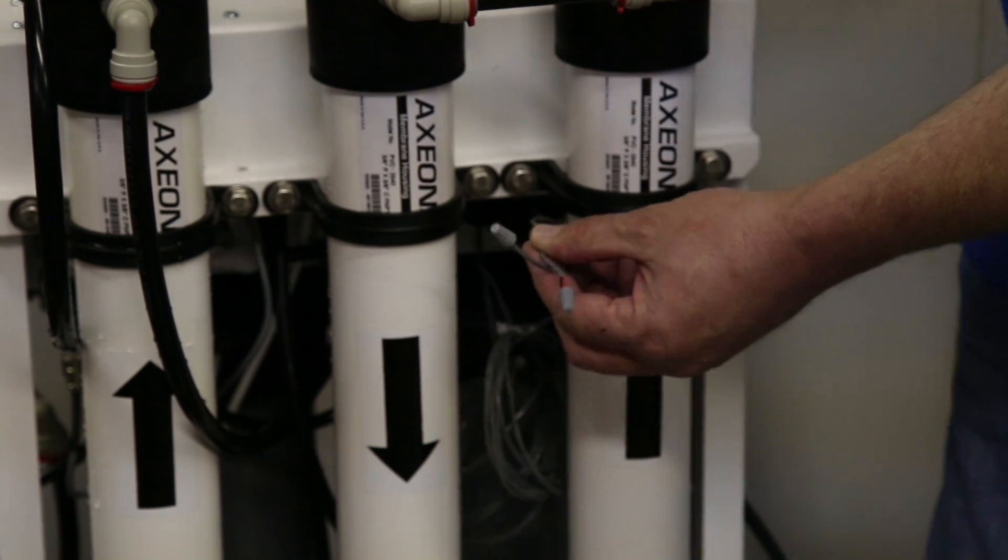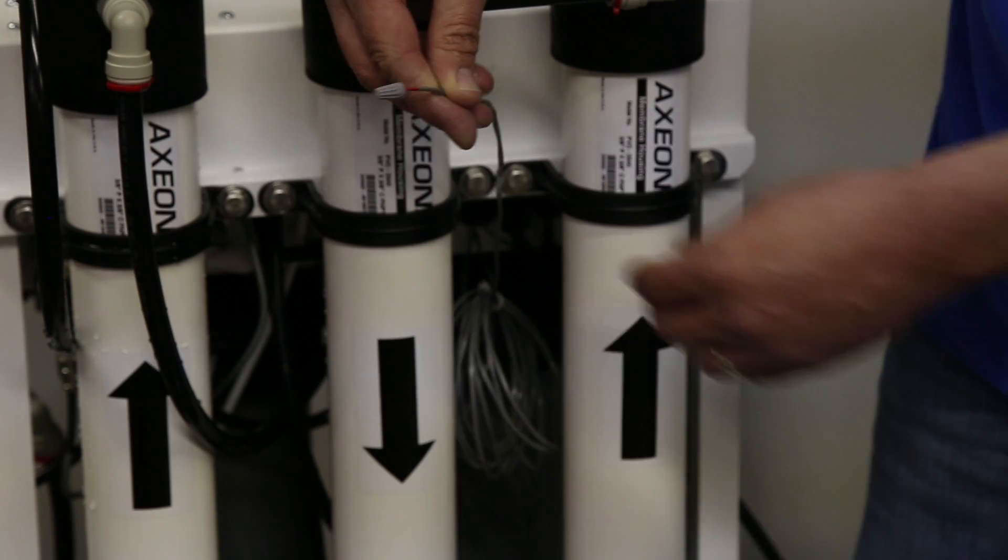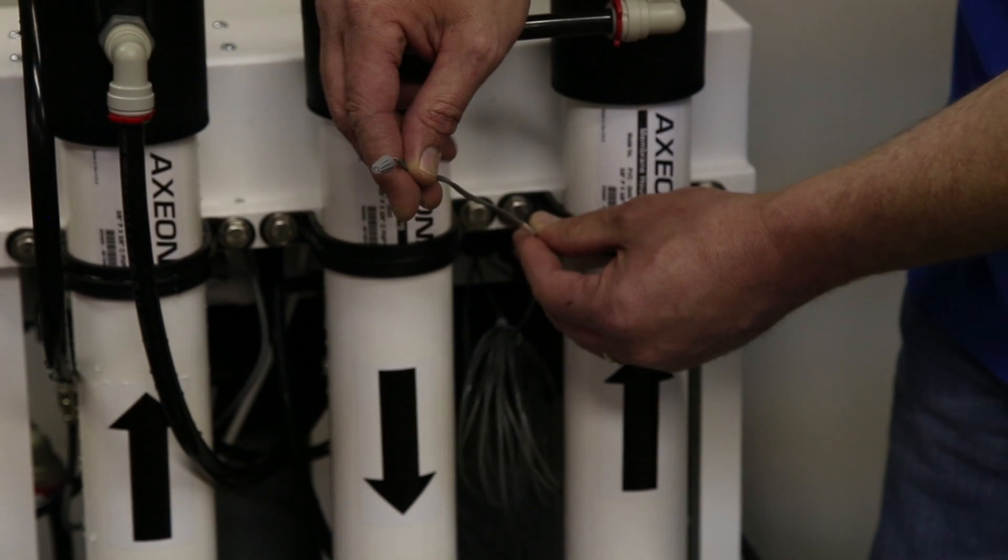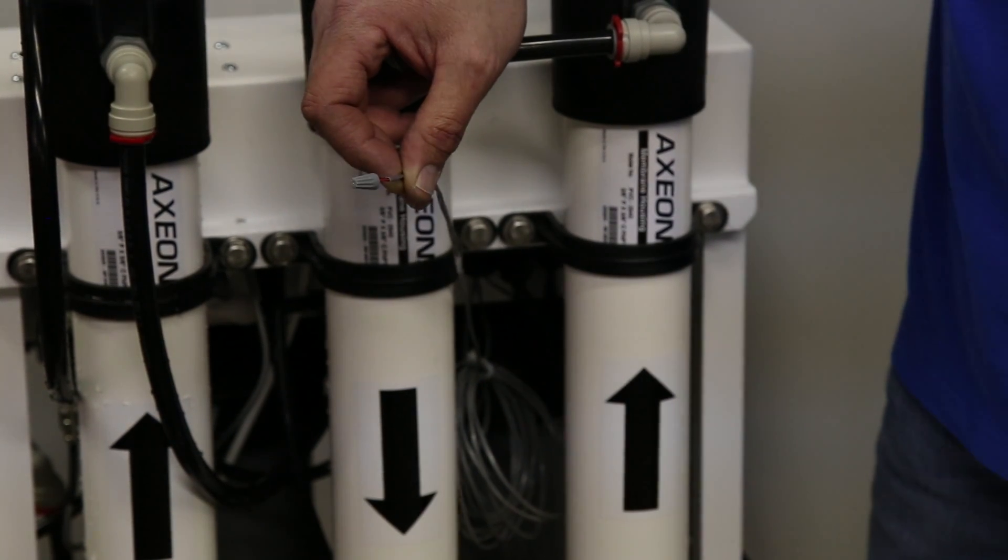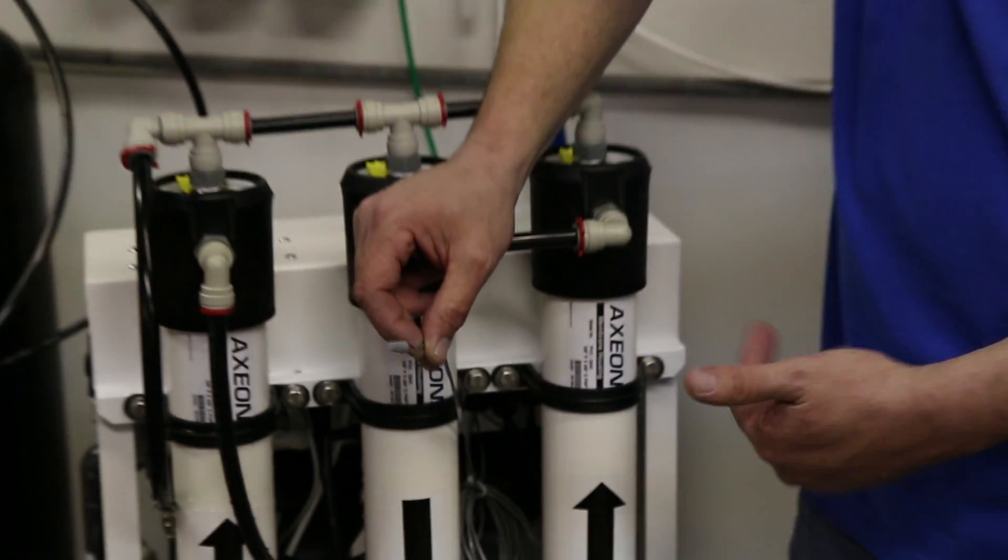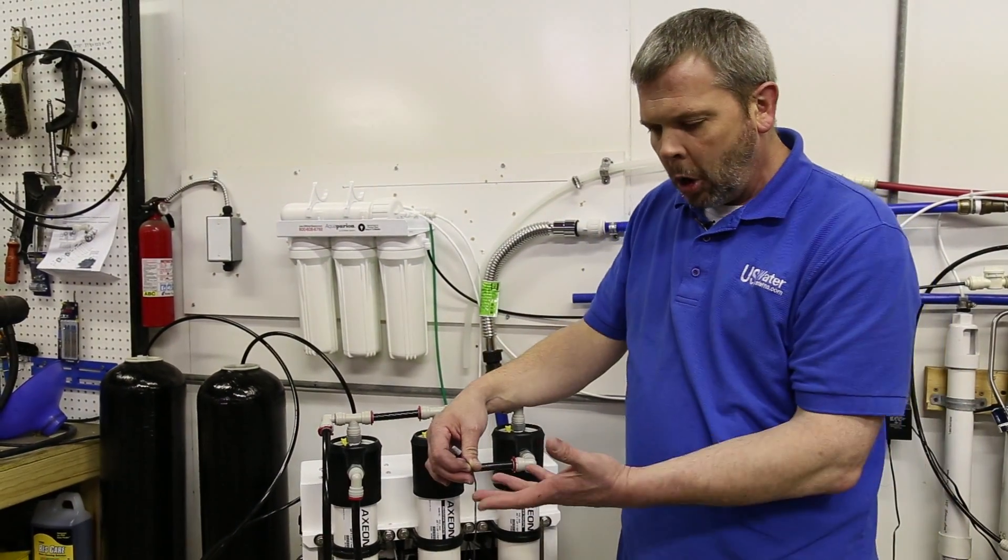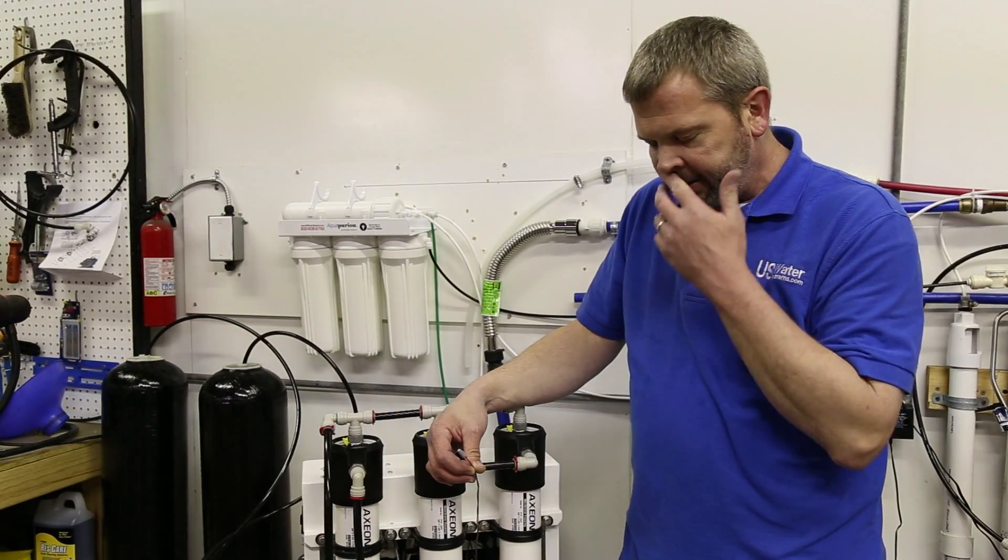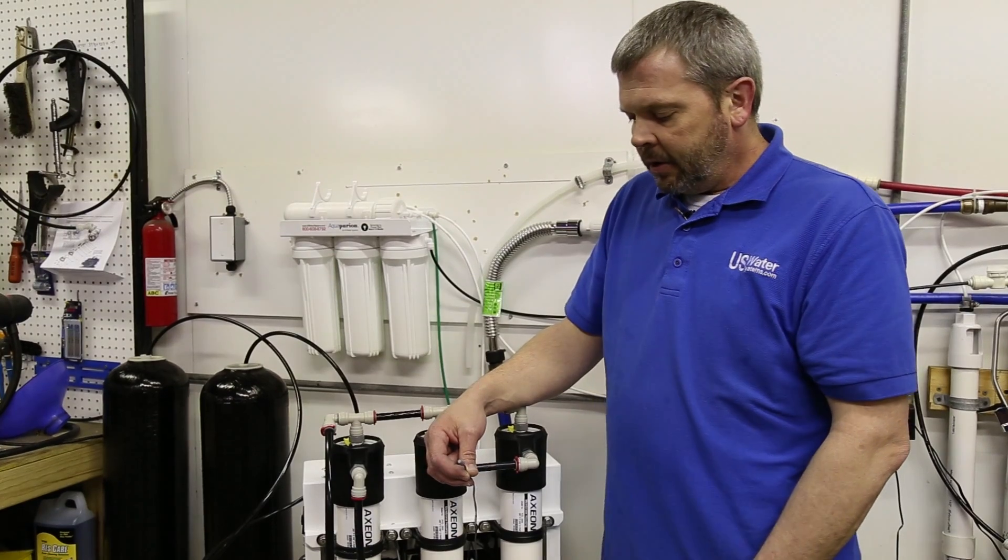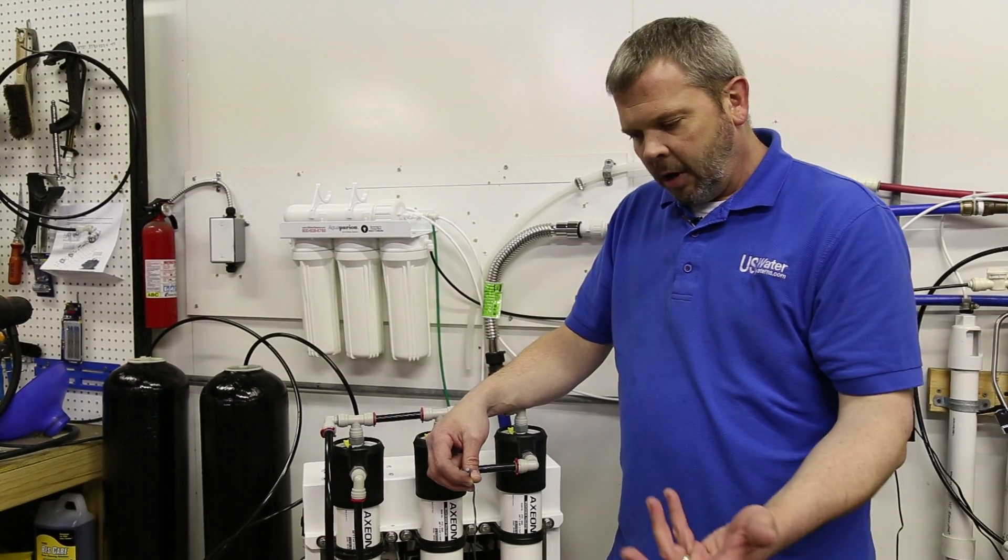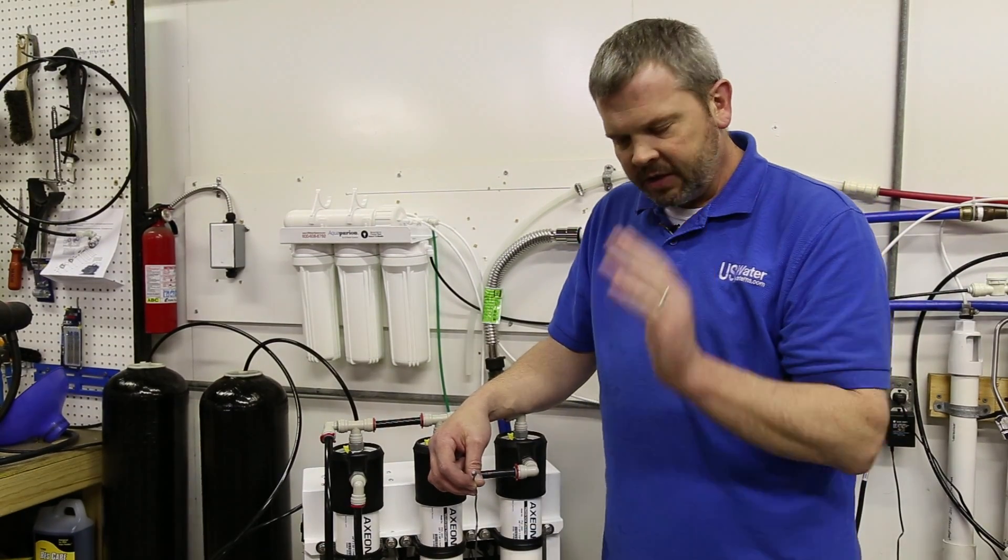The one for the tank full would be the one that you would run to a float switch in the tank. What that basically would do is it could be any kind of switch, any kind of wire size because again there's no voltage or amperage here. When this particular circuit is open and the wires aren't touching, then the system will not run. So you would want a switch that would open basically when the float comes all the way up and the tank is full.